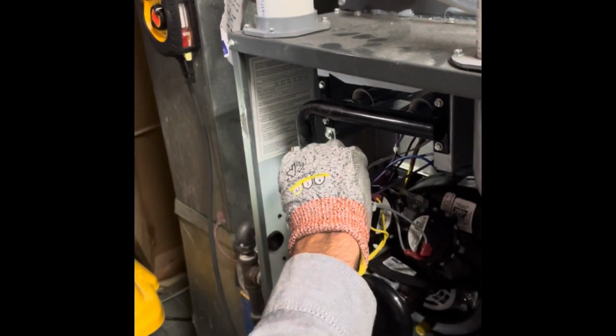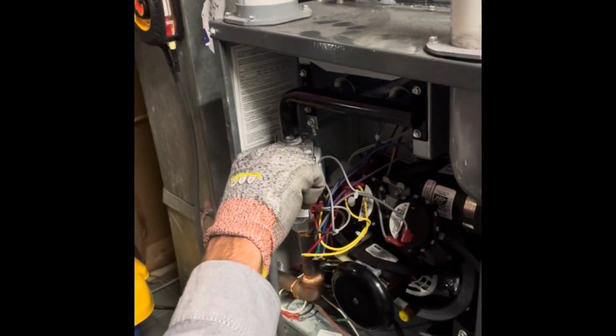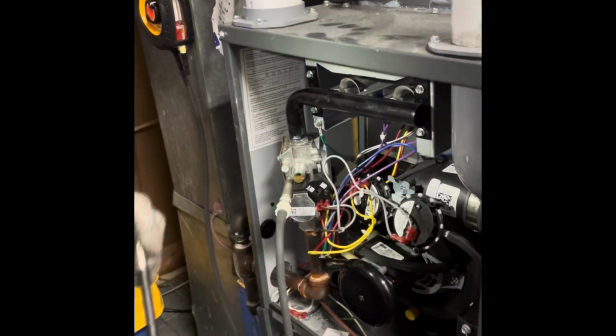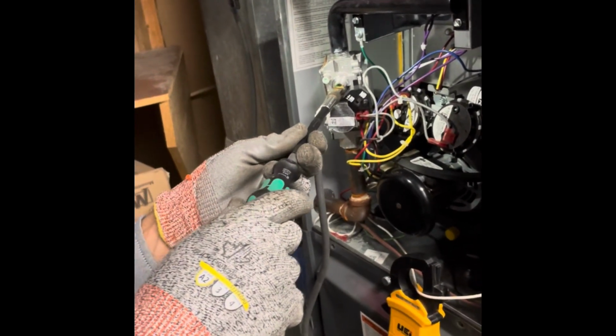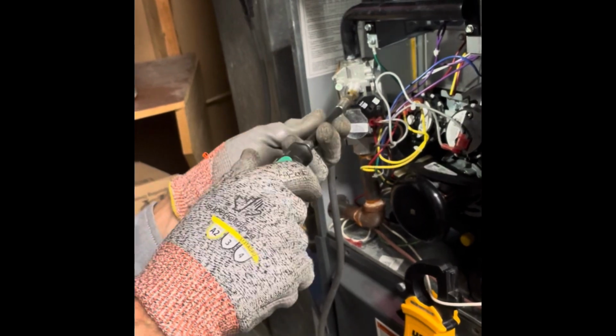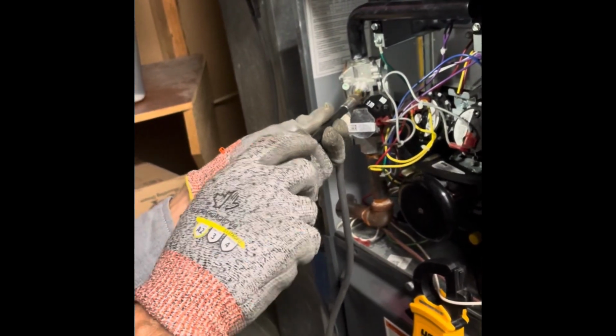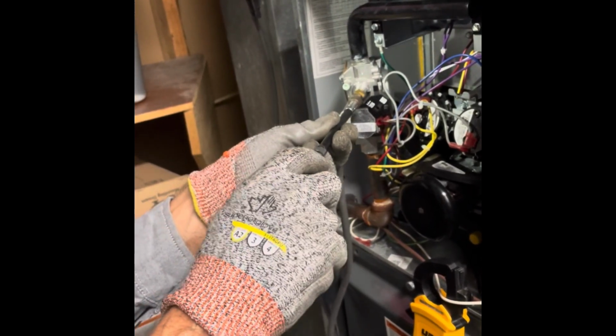So I've just got to try to get this little cap back in place. This is just a dust cap. It keeps the dust from going into where we have to adjust the valve. These things, you don't want to crank them tight. Just snug, that way if they ever need adjustment, we can take that out without wrecking it.